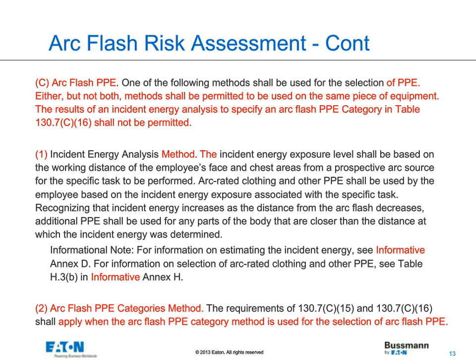In an Annex H, there are some informative annexes that show you how to select PPE based upon the incident energy analysis. And in part two, it talks about using the arc flash PPE category method. So that used to say hazard risk category. Now it's referred to as the arc flash PPE category method. And it just allows you to use that and select the PPE appropriate for that.